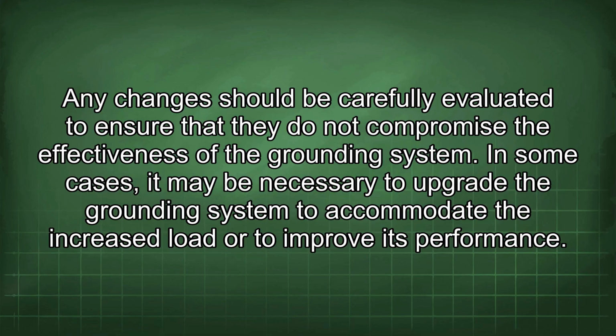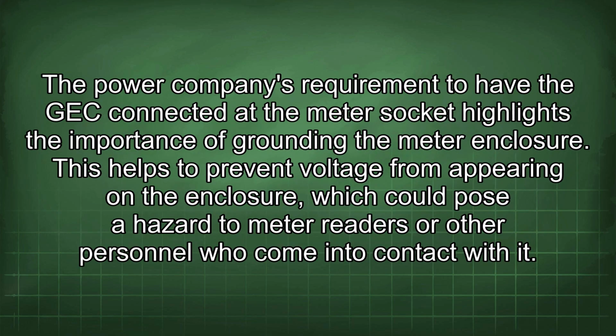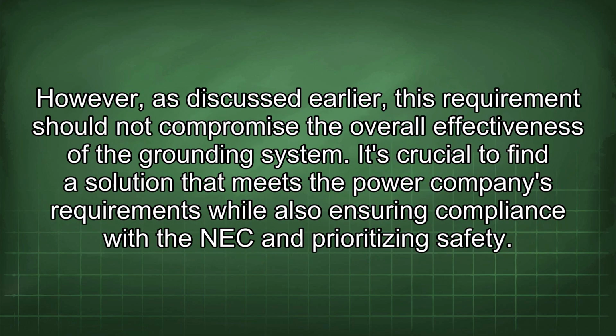In some cases, it may be necessary to upgrade the grounding system to accommodate the increased load or to improve its performance. The power company's requirement to have the GEC connected at the meter socket highlights the importance of grounding the meter enclosure. This helps to prevent voltage from appearing on the enclosure, which could pose a hazard to meter readers or other personnel who come into contact with it. However, as discussed earlier, this requirement should not compromise the overall effectiveness of the grounding system.